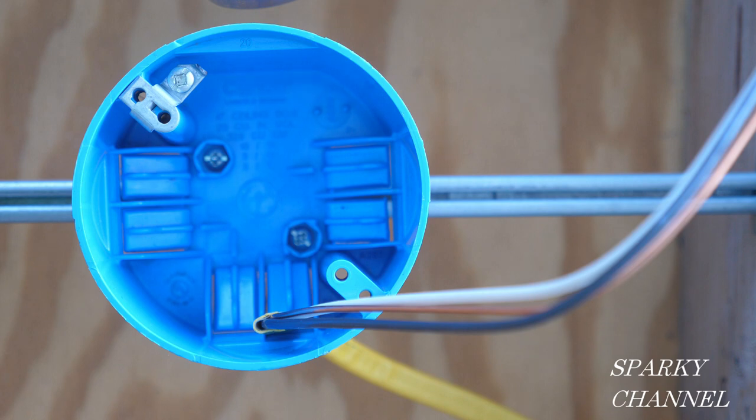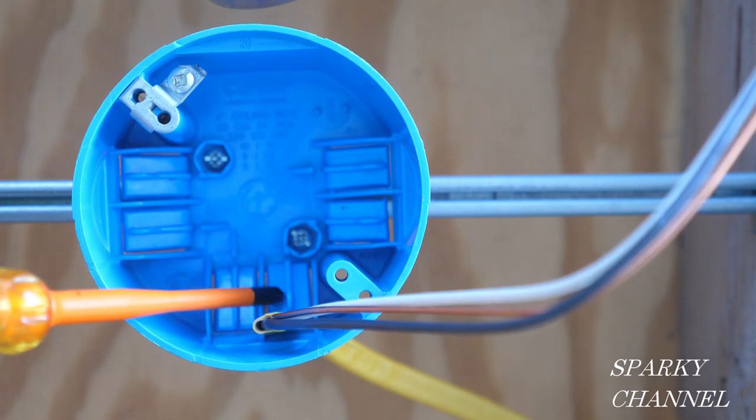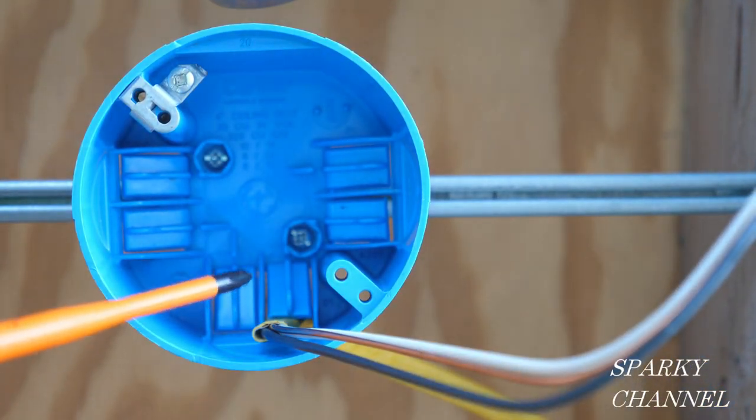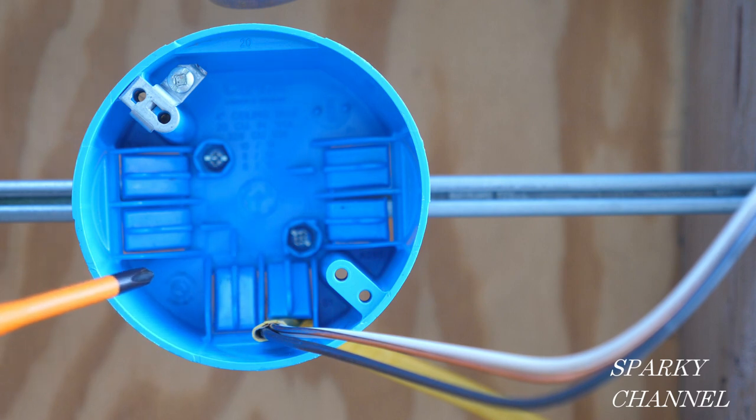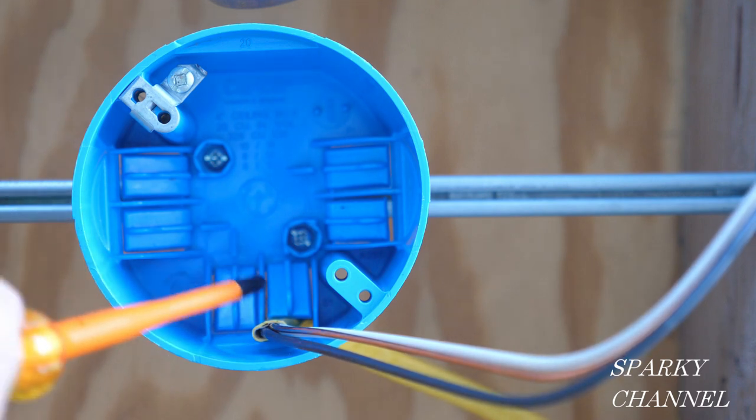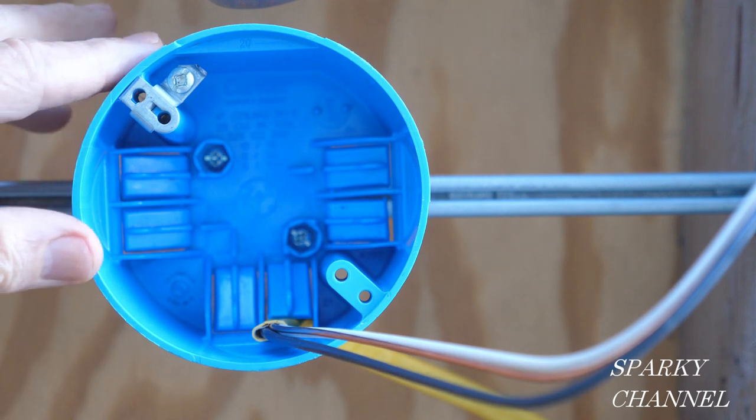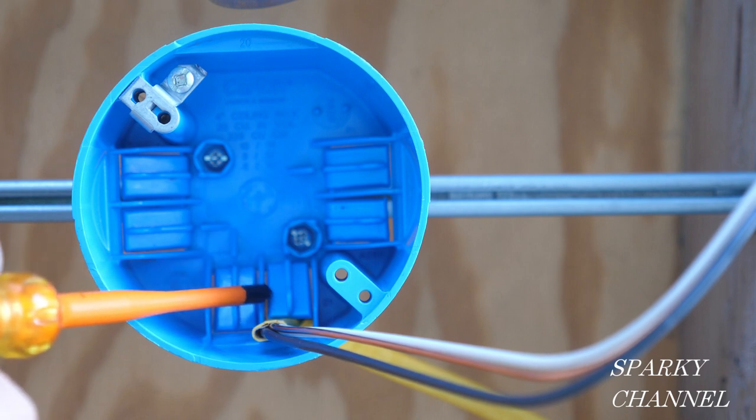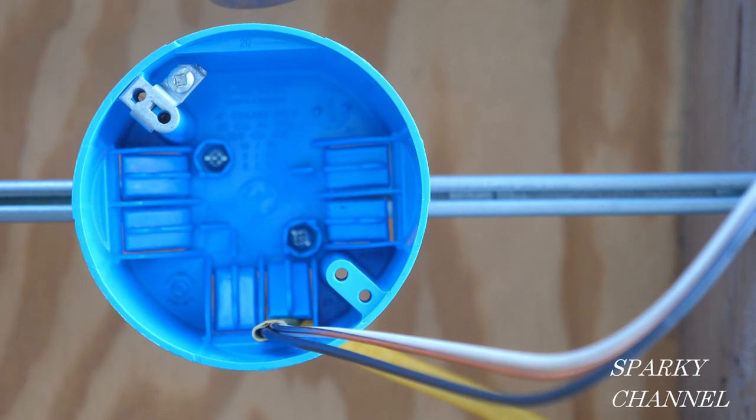My question to you is, do you think that this clamp right here, this integral clamp, is considered to be an interior clamp in the 2020 NEC? Because we need to know when we do box fill calculation, we need to know if this is counted as an interior clamp or not. We need clarity. Let's look in the actual 2020 NEC code and let's look for clarity on this.